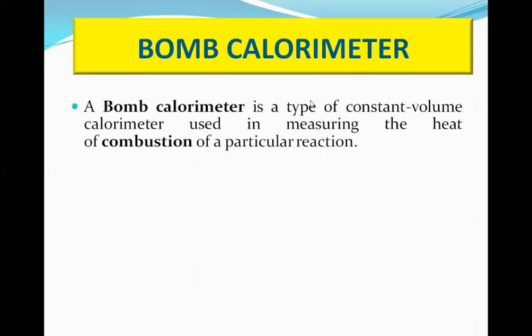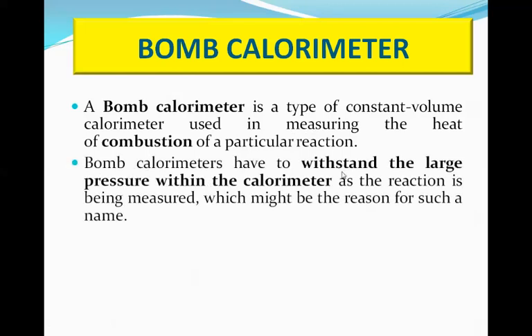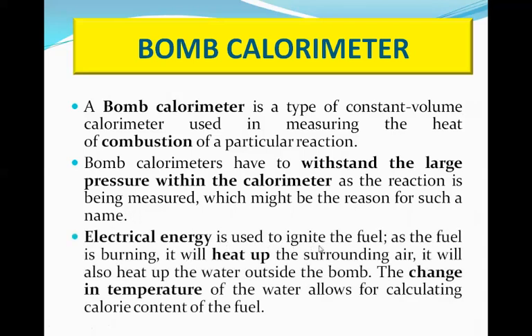Now we will discuss the instrument used to calculate the calorific value of solid and liquid fuels — the bomb calorimeter. It is a type of constant volume calorimeter used to measure the heat of combustion of a particular reaction. The bomb calorimeter has to withstand large pressure within the calorimeter; when a substance is burned inside the stainless steel vessel, a very high pressure is produced, which is why the word 'bomb' is used. Electrical energy is used to ignite the fuel. As the fuel burns, it heats up the surrounding air and the water outside the bomb, and the change in temperature of the water allows for calculating the calorie content of the fuel.